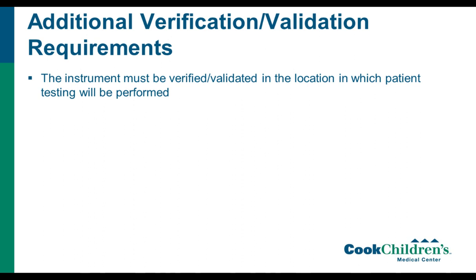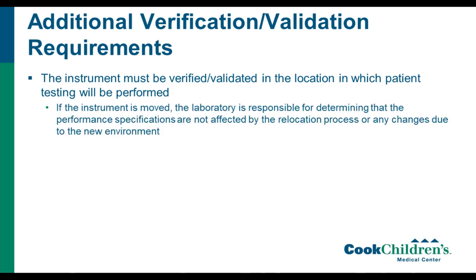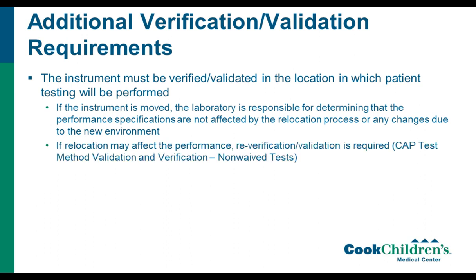In addition to those specific requirements, there are also a couple more requirements. So one is that the instrument must be verified or validated in the location in which patient testing will be performed. So if you validate it in one place and move it somewhere else, you have to determine if that will affect the performance of the assay. And so CAP is a little bit gray on this, and they don't give definitions of, if it's moved over 25 feet to a new building. They don't specifically say, but the lab is responsible for determining if moving it may affect the performance of the assay.